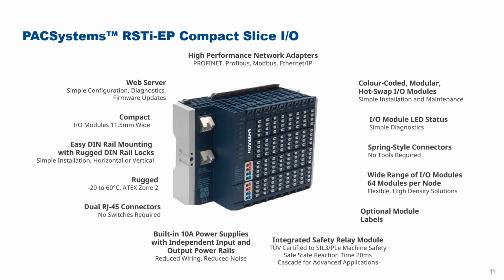These support -20 to 60 degrees C operation with ATEX Zone 2 conformance. And we also simplify the wiring with built-in 10 amp power supplies with independent input and output power rails through the network adapter. This reduces the overall wiring required and also reduces crosstalk and noise between channels.